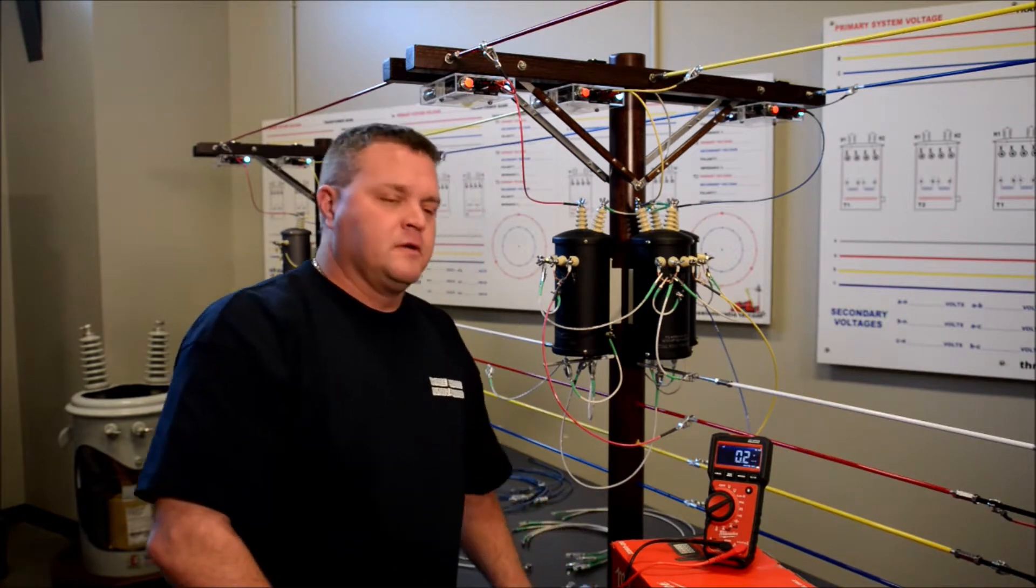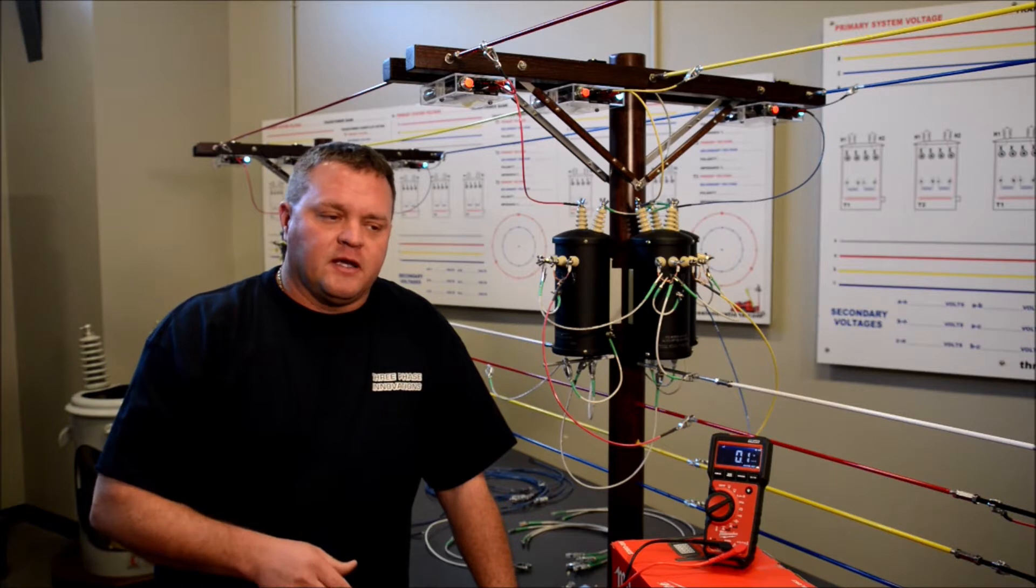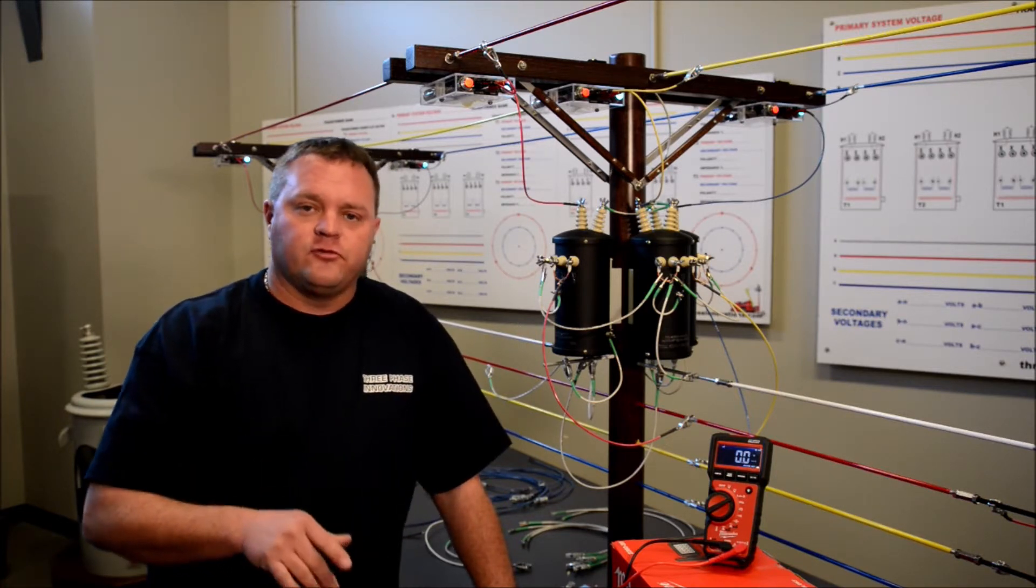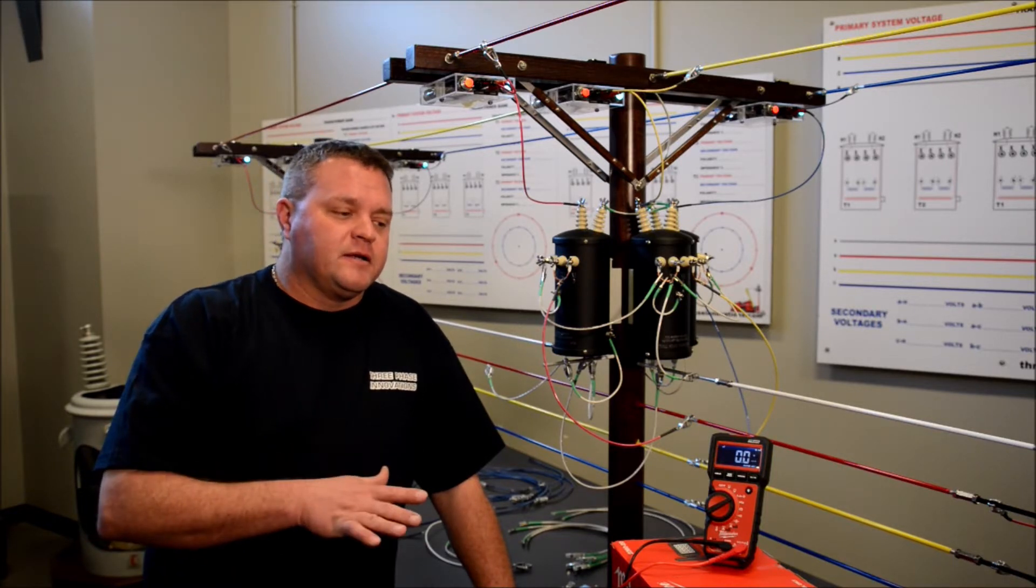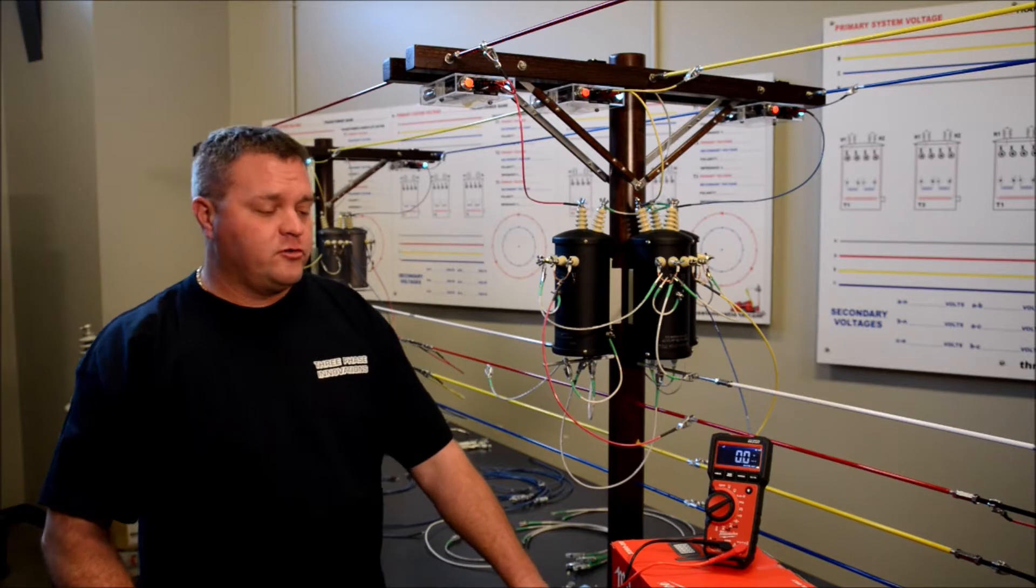We can see that the voltage has increased. Actually the scenario that we were told to happen with this kind of voltage - it was enough to go inside a building and burn quite a bit of equipment up. So this is why we always tie a wye-wye bank.